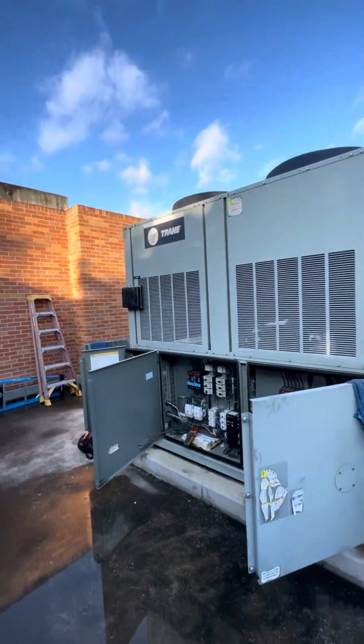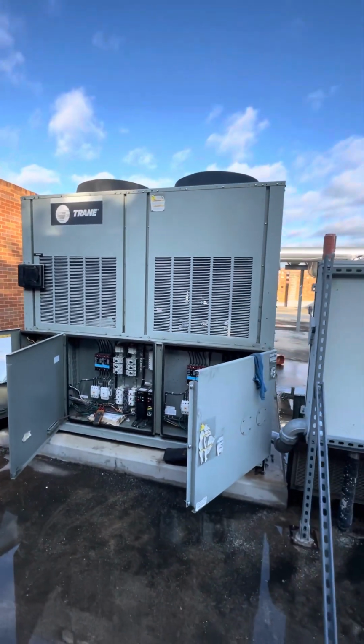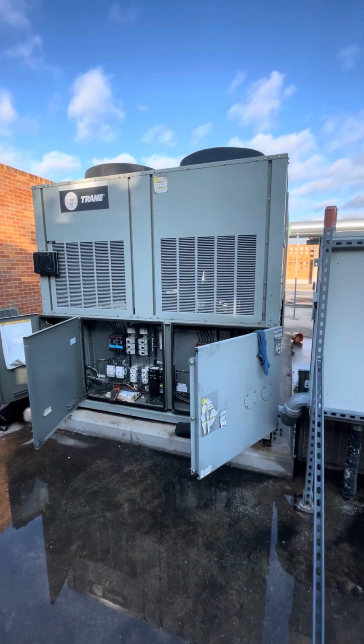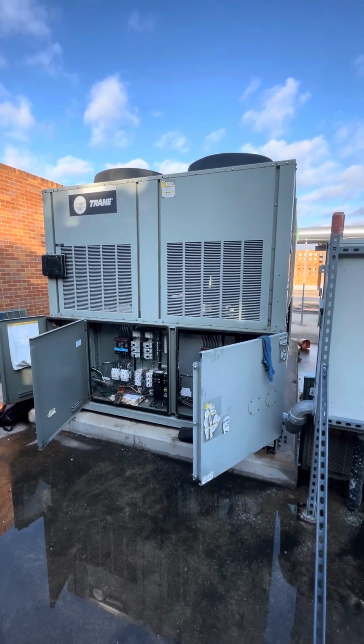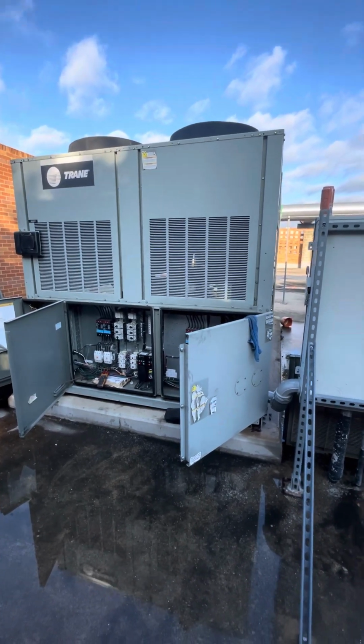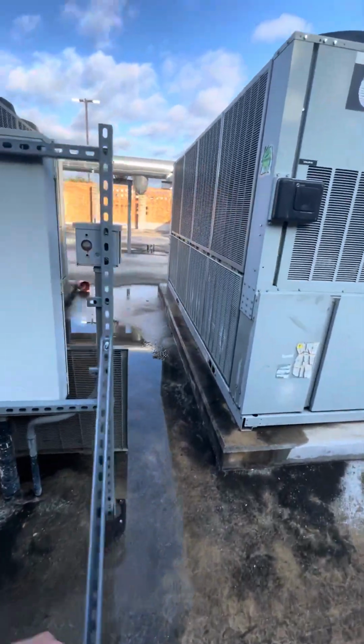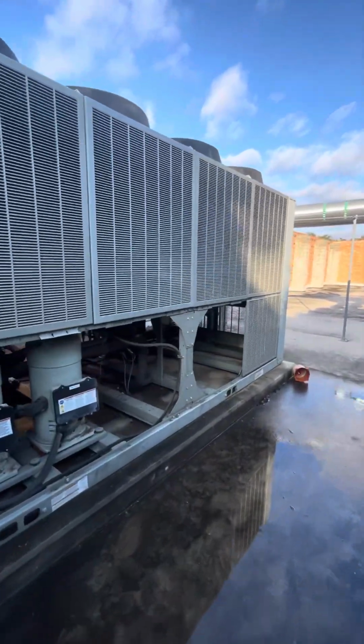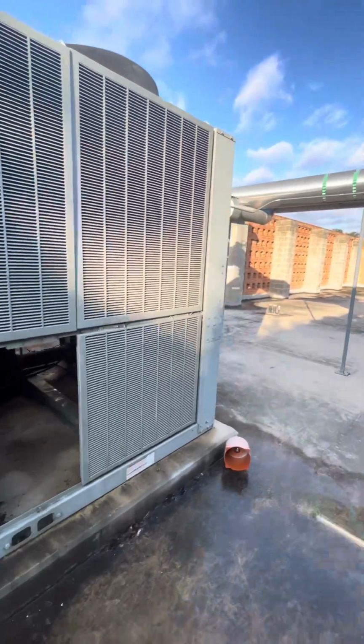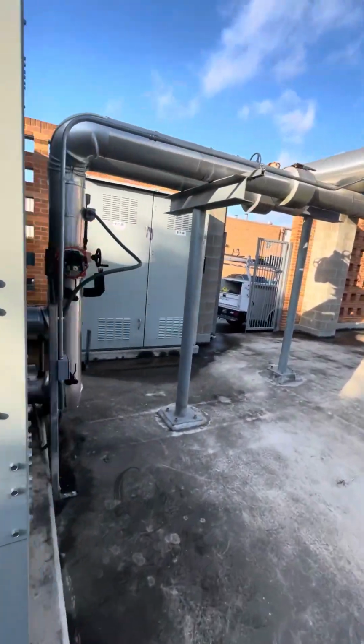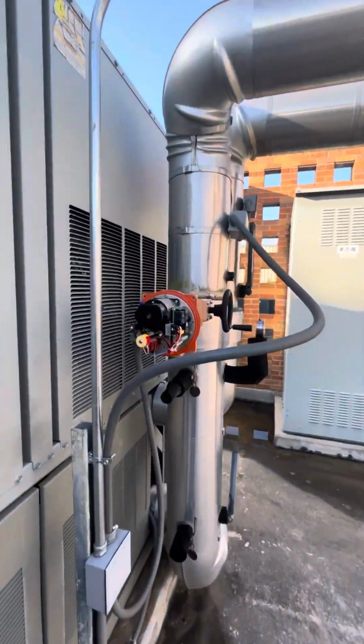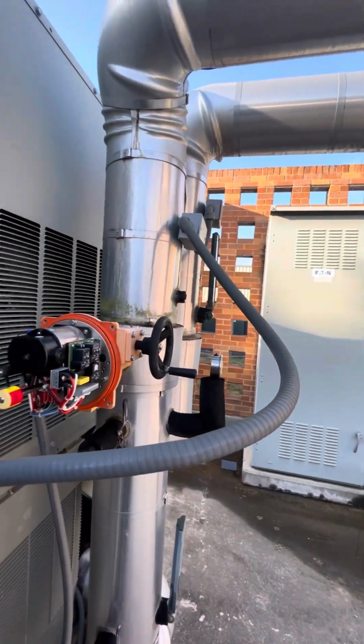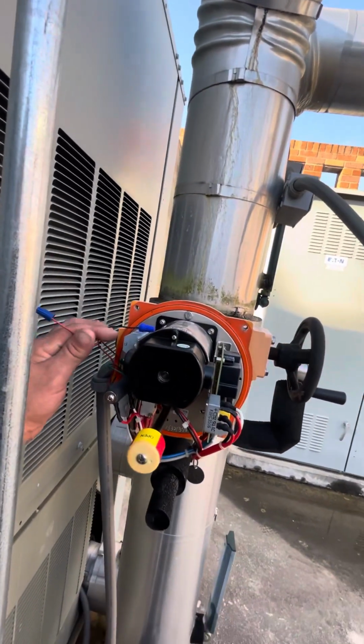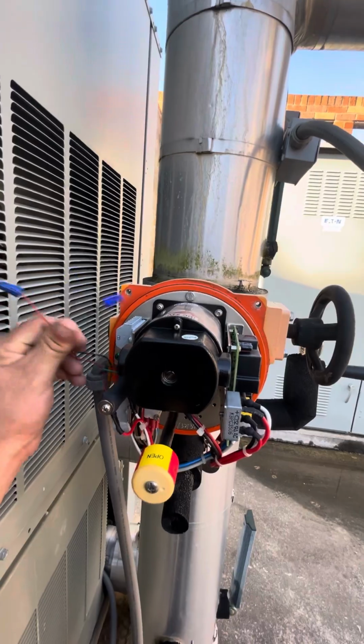We're going through and doing a maintenance here for this customer. It's not really a maintenance, it's more of an assessment. They haven't run these chillers in who knows how long, and they've got a series of faults. Their building automation is screwed up, so we're trying to get these things mechanically sound before they get their building automation situation sorted out. Basically we have a chilled water isolation valve there.